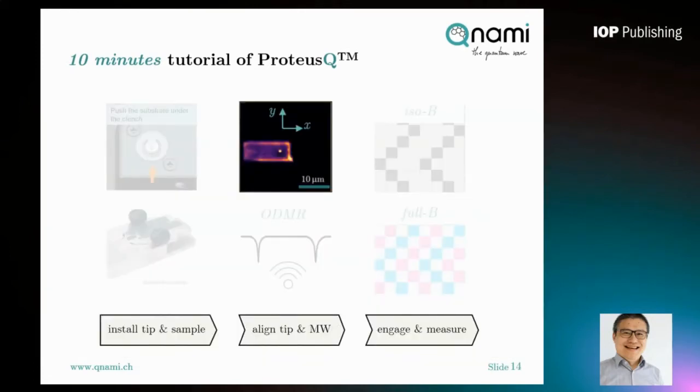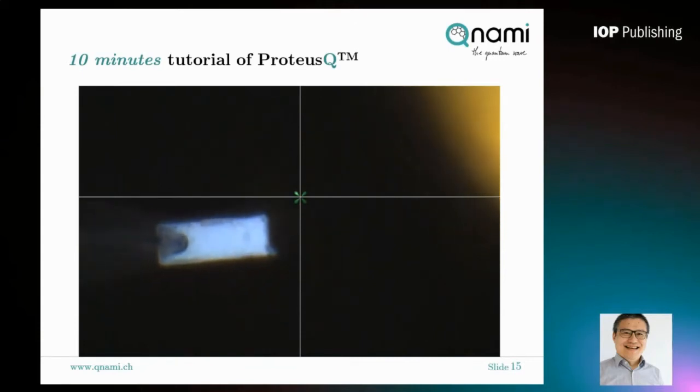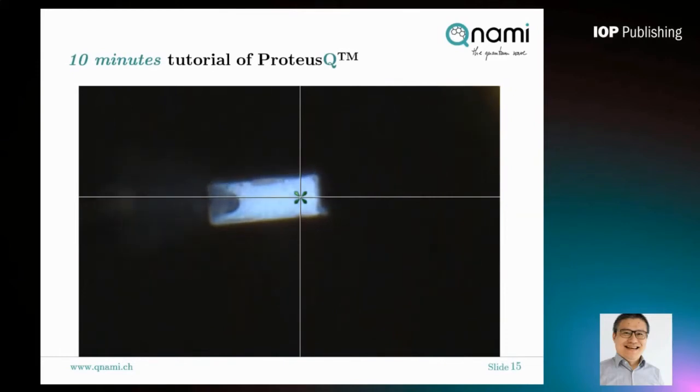After inserting the probe holder into ProteusQ, the next critical step is to align the probe optically to the confocal axis and perform a confocal scan of the cantilever. Using the built-in top camera, we can easily see the cantilever as well as part of the microwave antenna, which is tens of microns away. The dark feature in the cantilever image indicates the diamond pillar position. We then open the laser spot indicator, move the cantilever in the X and Y direction, make sure the image is focused, and switch the mirror on the microscope to the confocal path.